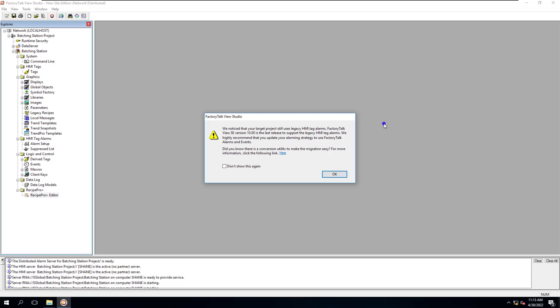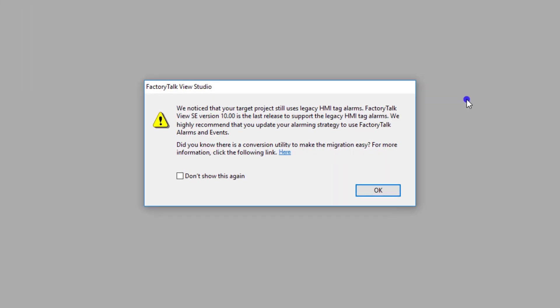Have you ever opened up your Factory Talk HMI application and seen this window? It's basically notifying you that legacy alarm HMI tag alarms will no longer be used after Factory Talk 10. They will still be accepted and used on Factory Talk 10, but when you're moving forward to Factory Talk 12 or above, they will no longer be used. What they want you to do is utilize this tool and move those to an alarms and events structure.